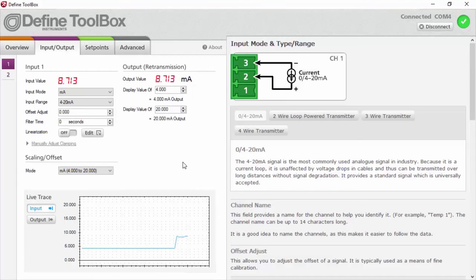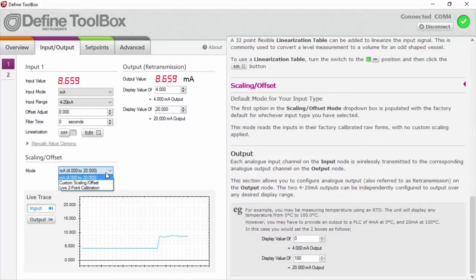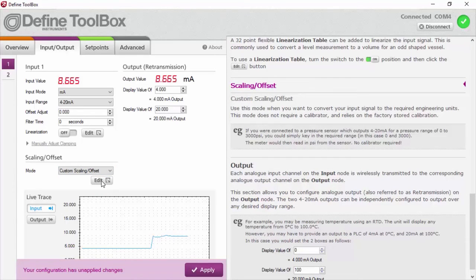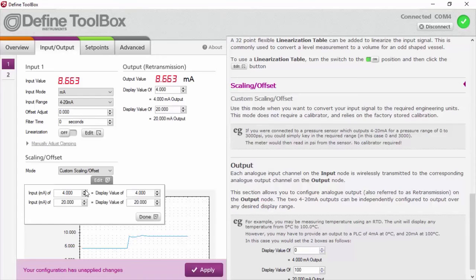So that's great if I wanted to know what the value was in milliamps, but I'd prefer it to be in something human readable. So to make it a bit easier for me to understand what's going on, I'm going to go down to our scaling and offset heading here, and I'm going to pick custom scaling. Custom scaling is going to let me show the input value here. I want to show it in feet. So that's feet of water in the tank from 0 to, let's say, 20 is the top of my tank. So if I click edit, I can see here input milliamps of 4 milliamps is a display value at the moment of 4, and input of 20 at the moment is 20. So that's straight, no scaling.